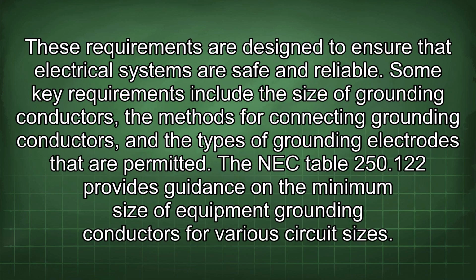These requirements are designed to ensure that electrical systems are safe and reliable. Some key requirements include the size of grounding conductors, the methods for connecting grounding conductors, and the types of grounding electrodes that are permitted. The NEC Table 250.122 provides guidance on the minimum size of equipment grounding conductors for various circuit sizes.